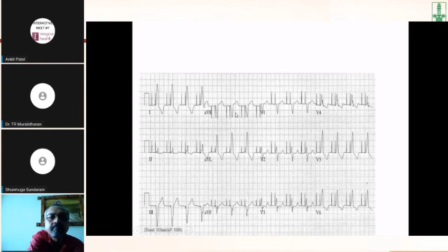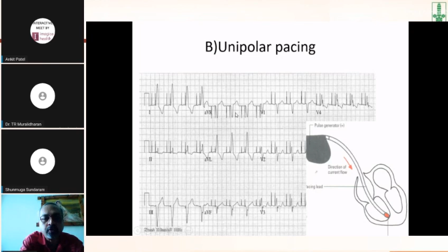On the right, you have the cartoon where the negative electrode, the cathode, is in contact with the endocardium, the positive pole being with the pulse generator, and you can see the current flows from the positive to the negative. It has to travel a long distance, hence it generates a big pacing spike. So it is very important to know what causes a small or negligible spike, and why you get a big spike with unipolar pacing. So this is a normal phenomenon. Next.